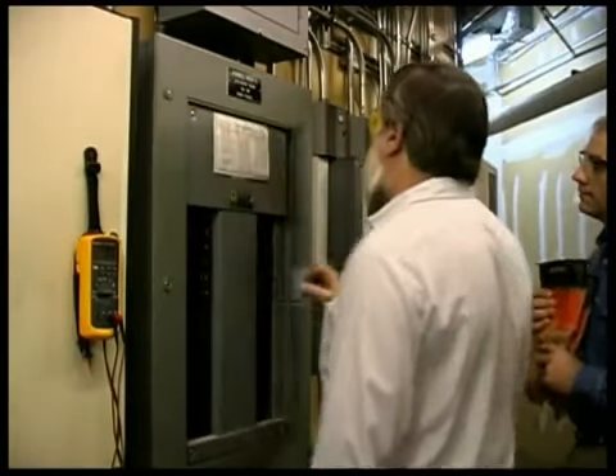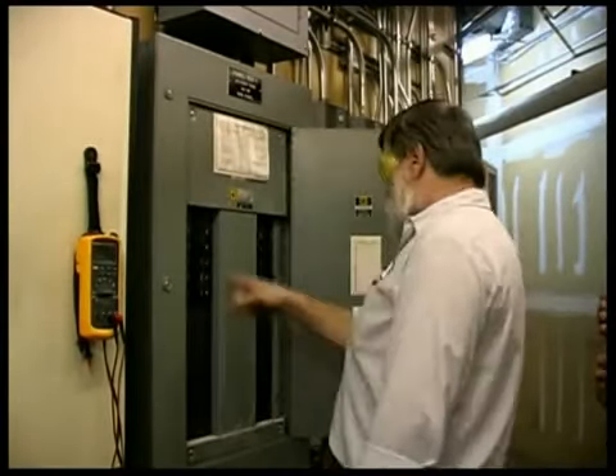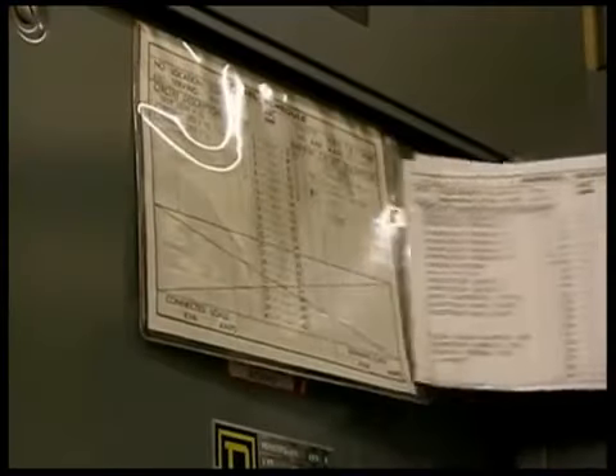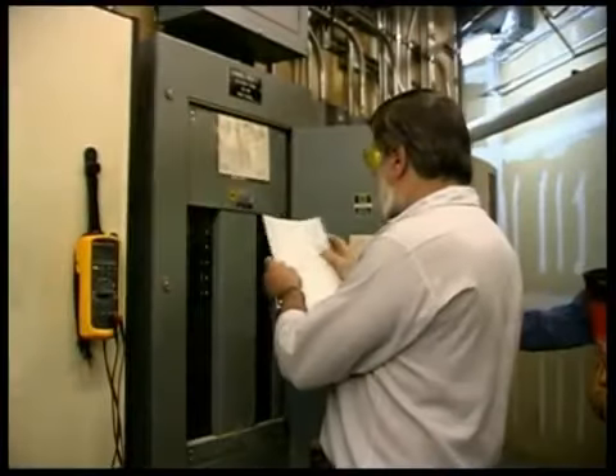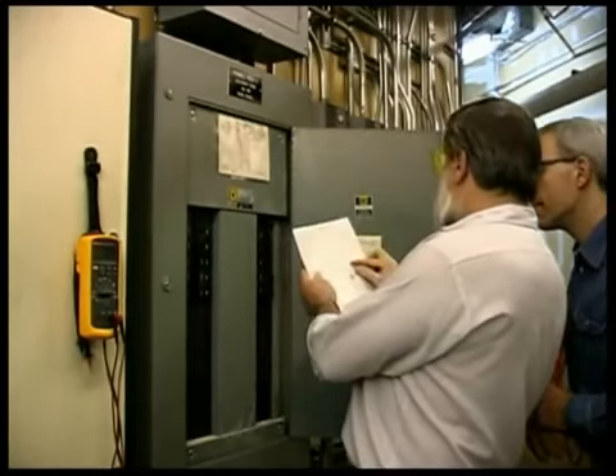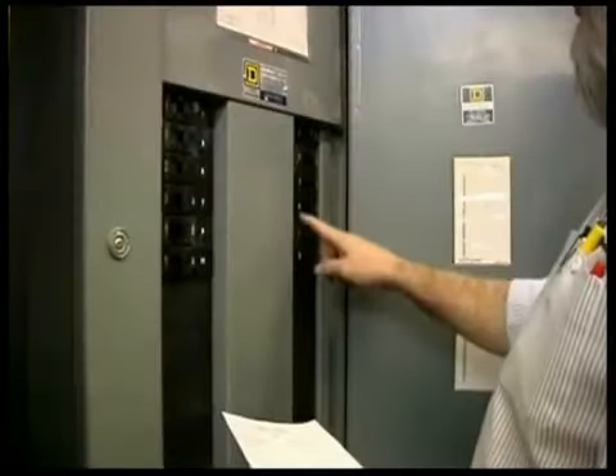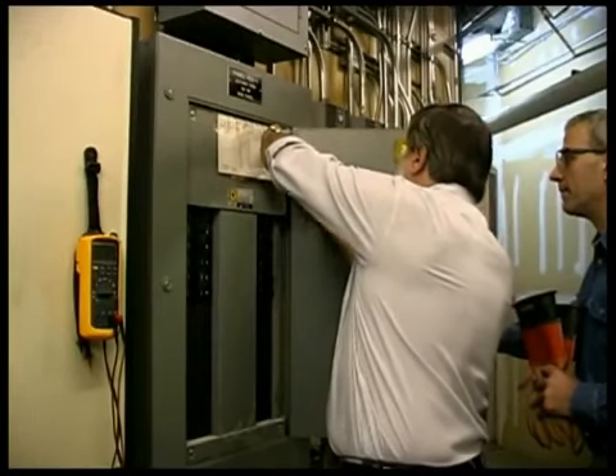The safest place to measure is where the lowest energy is available. For example, if you're measuring voltage on a breaker panel, identify the lowest rated breaker and make your measurement there. This way, you have more protection between yourself and the potential hazard.